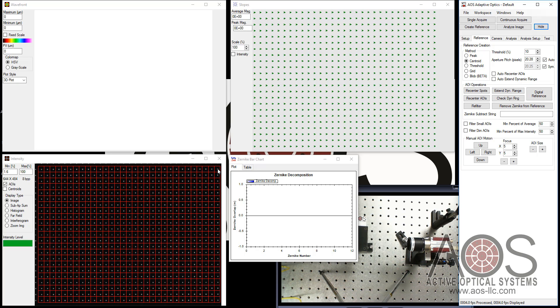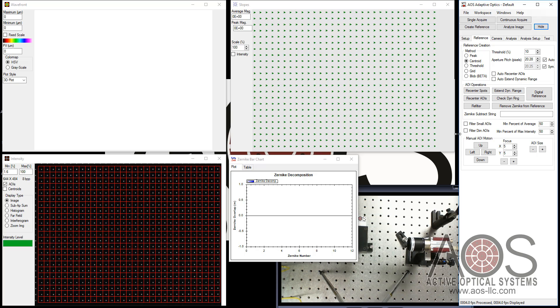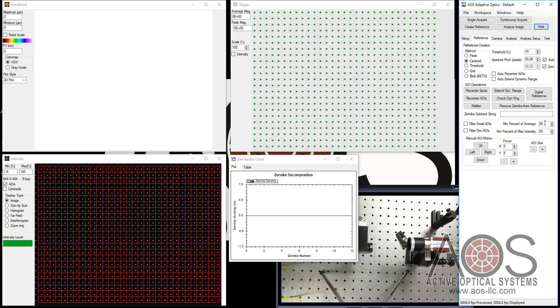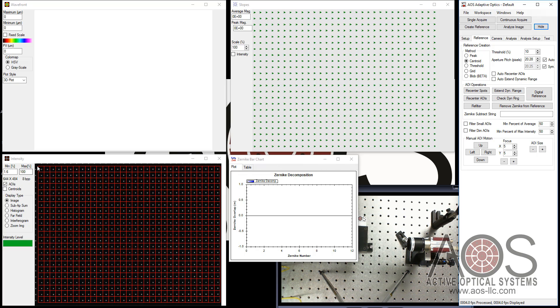The only thing I see that I'm concerned about right now is that some of the spots toward this edge are very close to the edges of their AOIs or closer than I'd like. What I can do is I can filter the AOIs using the filtering mechanisms for small and dim AOIs. Since the beam is pretty uniform, the dim one is not going to be very useful. The small one might be. But you can see that the size of these AOIs is pretty much the same as the rest of them. So that's not going to be terribly useful either.